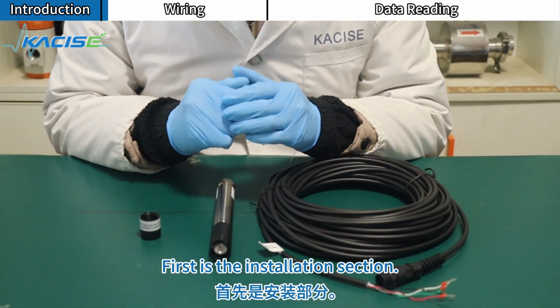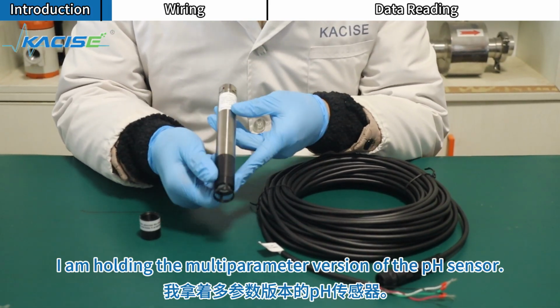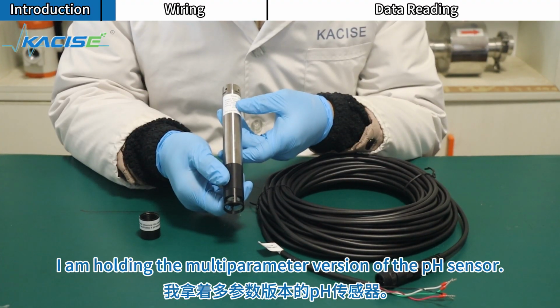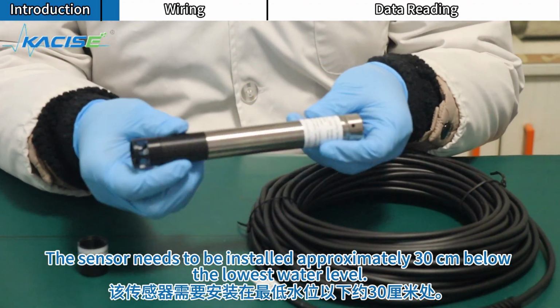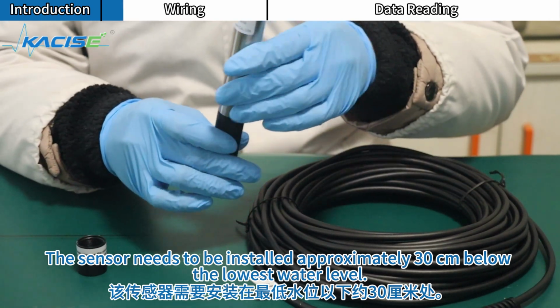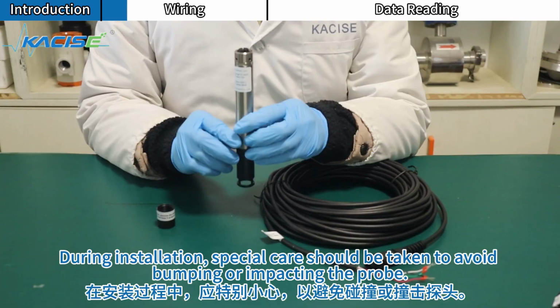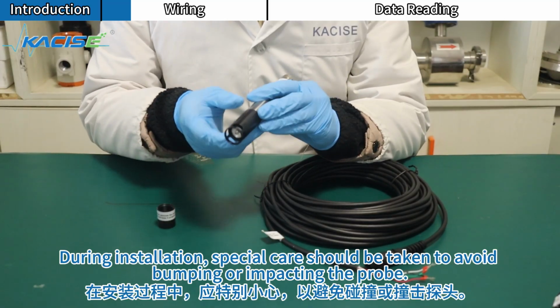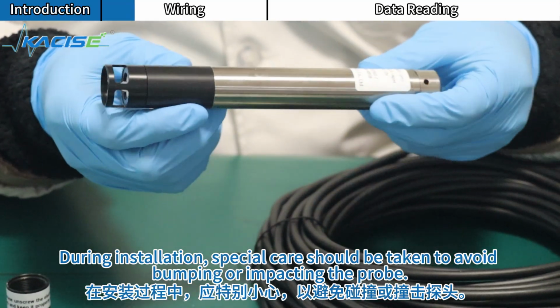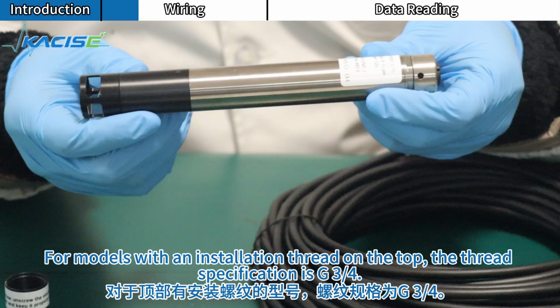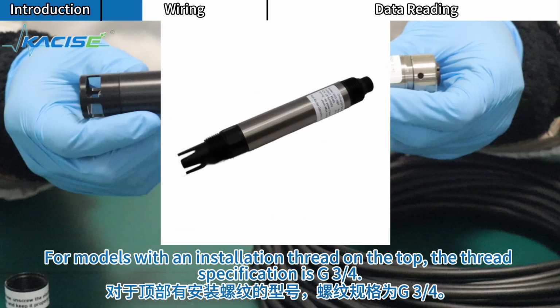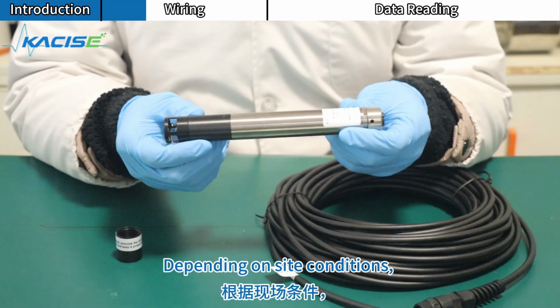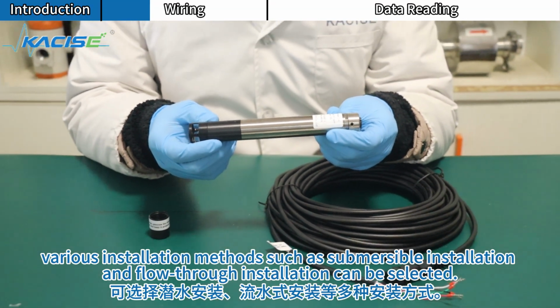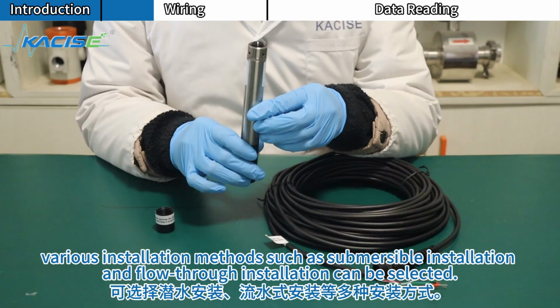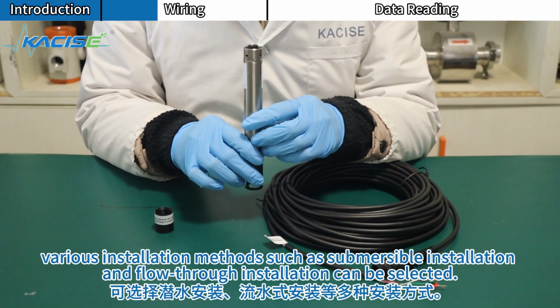Installation and wiring. First is the installation section. I am holding the multi-parameter version of the pH sensor. The sensor needs to be installed approximately 30 centimeters below the lowest water level. During installation, special care should be taken to avoid bumping or impacting the probe. For models with an installation thread on the top, the thread specification is G3/4. Depending on site conditions, various installation methods, such as submersible installation and flow-through installation, can be selected.